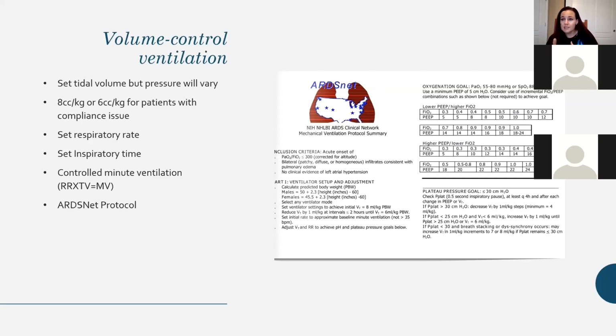But if you are shooting for 8 cc's per kilo and your patient just isn't tolerating it, which means you're getting high pressure alarms on your vent, so if you set your peak inspiratory alarm at 40, it means they're hitting 40 every time. Once you hit that 40, a lot of people don't think about this, but it won't continue to give the breath. Your ventilator will cycle into exhalation. So if your ventilator has only given 50% of the tidal volume that you've set, and then it cycles into exhalation, your patient will be chronically underventilated over and over and over again. So you need to be really responsive to those alarms. And I have a whole slide in here about how to set the alarms and what to pay attention to with that kind of thing.